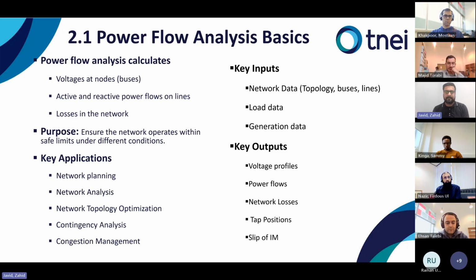In any network analysis, we need to do the load flow many times. The key inputs that we provide to the load flow solver are network data, that is topology, buses and lines, load data, and also the generation data. And the key outputs can be the voltage profile, power flows, network losses, tap positions of voltage regulators, and slip of the induction machine, etc.